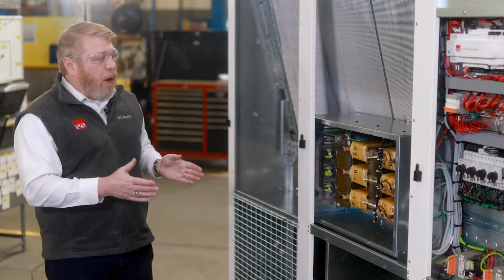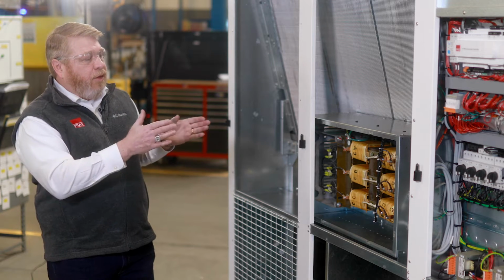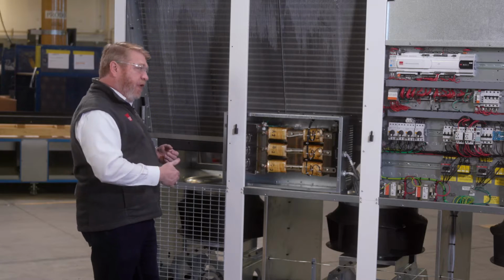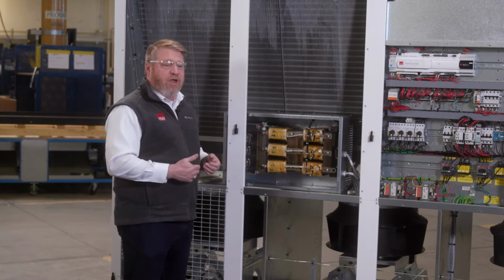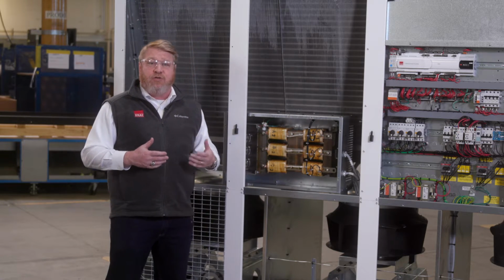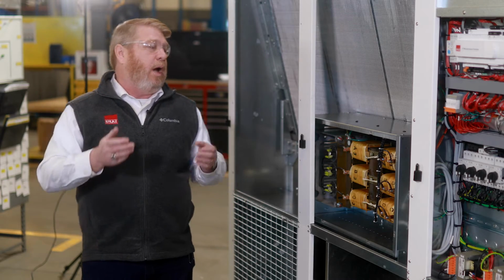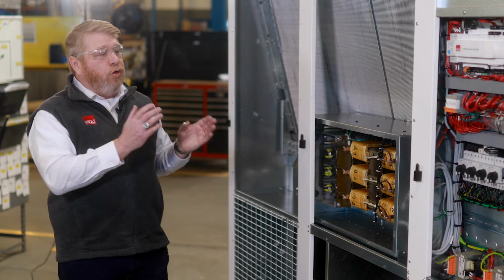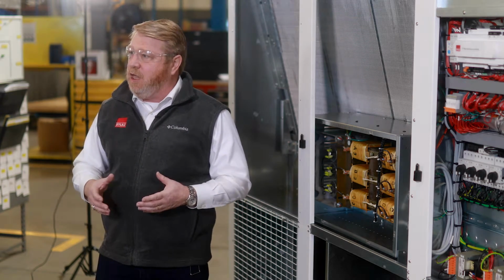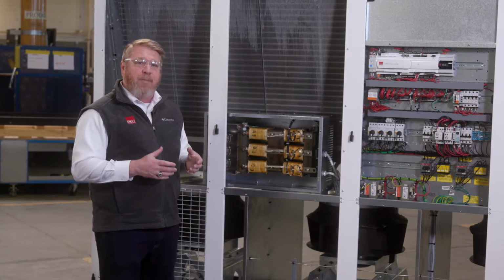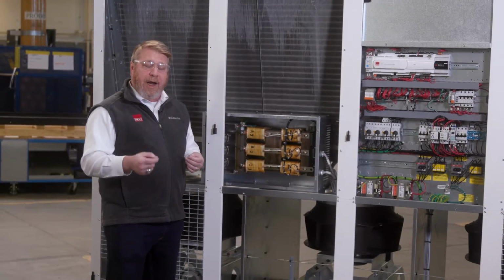Since we're able to control the speed of the device and match the load within the space, that is a positive. The negative, of course, is the fact that we develop what is known as total harmonic distortion. The best way to imagine this is that the power signal coming into the device has a fairly pure sine wave. Now, as we either electronically commutate or use the VFD to change the frequency, we see additional information added to that power wave at different harmonics.